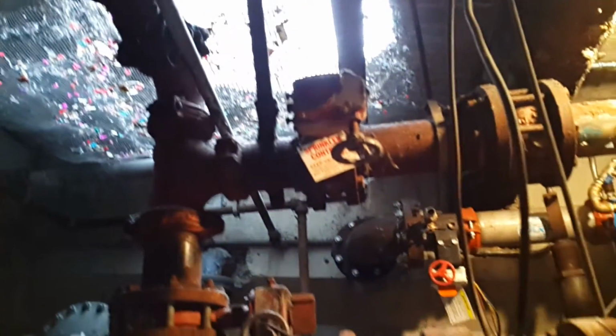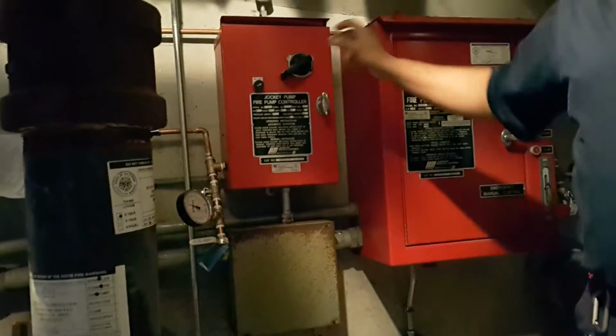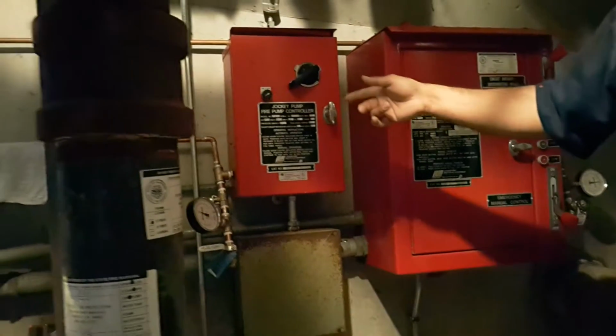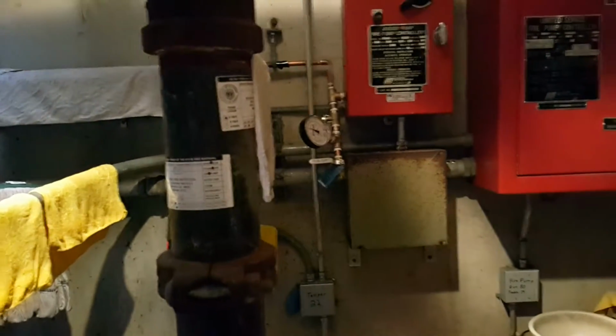This is called the fire pump bypass. So we still have water in case the fire pump does not turn on. You still have water in the building. You do have a jockey pump. There's your jockey pump controller. On these controllers, we do 2 tests. We do a manual test to just start it, make sure that it starts, and then we do a pressure drop test to test it automatically on both. We just write down the pressures, what they are. They start.